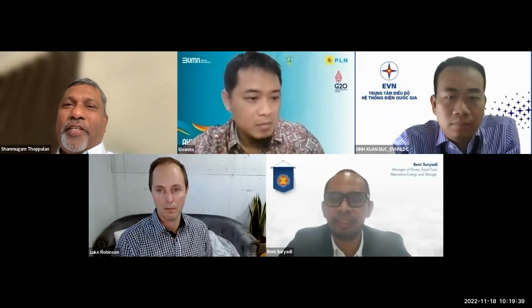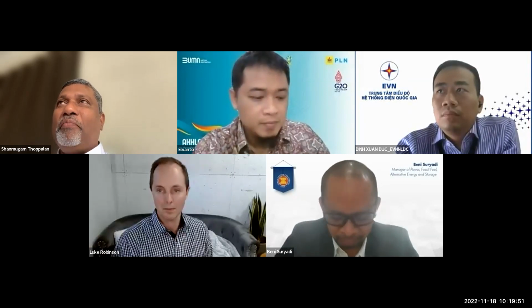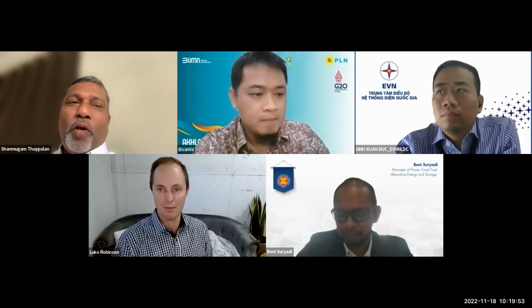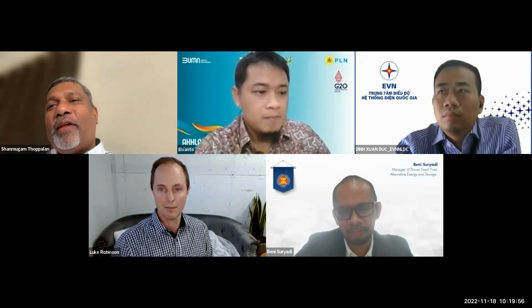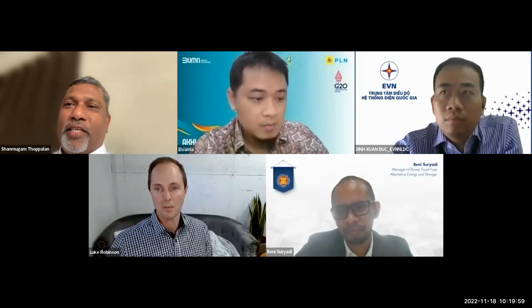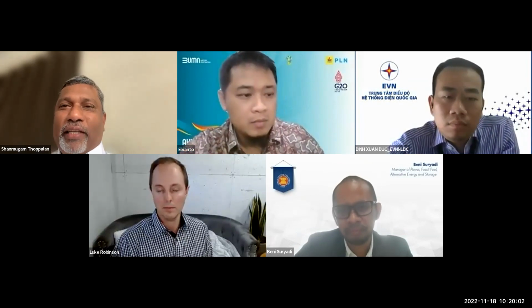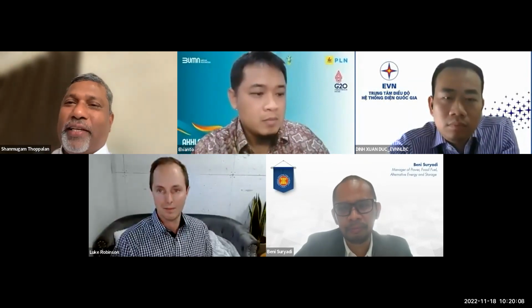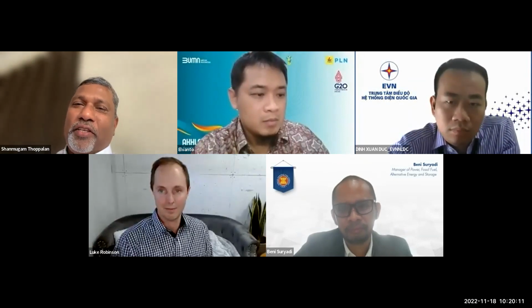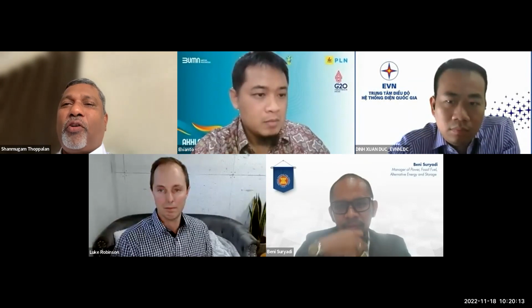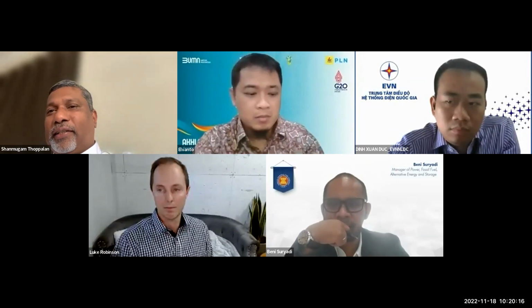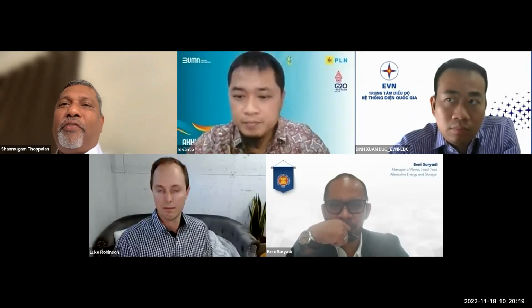Thank you. Yeah, Pak Ben, it's interesting. I think we are also coming across, as I mentioned earlier, new design machines where the level of robustness for rock-off is somehow limited, because they are designed for big systems. Our grid is robust enough for N-1, but our concern is multiple contingencies at the same time. How do we protect our grid beyond a 1 Hz per second situation? That's one challenge we worry about, how to manage this in future. That is why wide area protection and control is an important aspect, how we manage the defense scheme beyond conventional under-frequency.